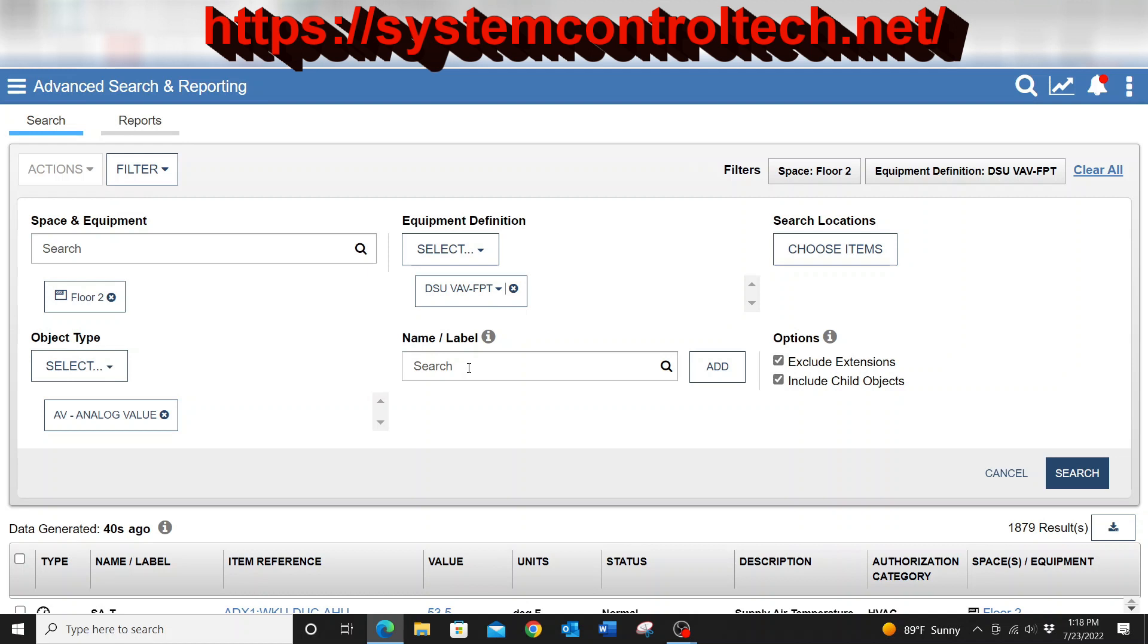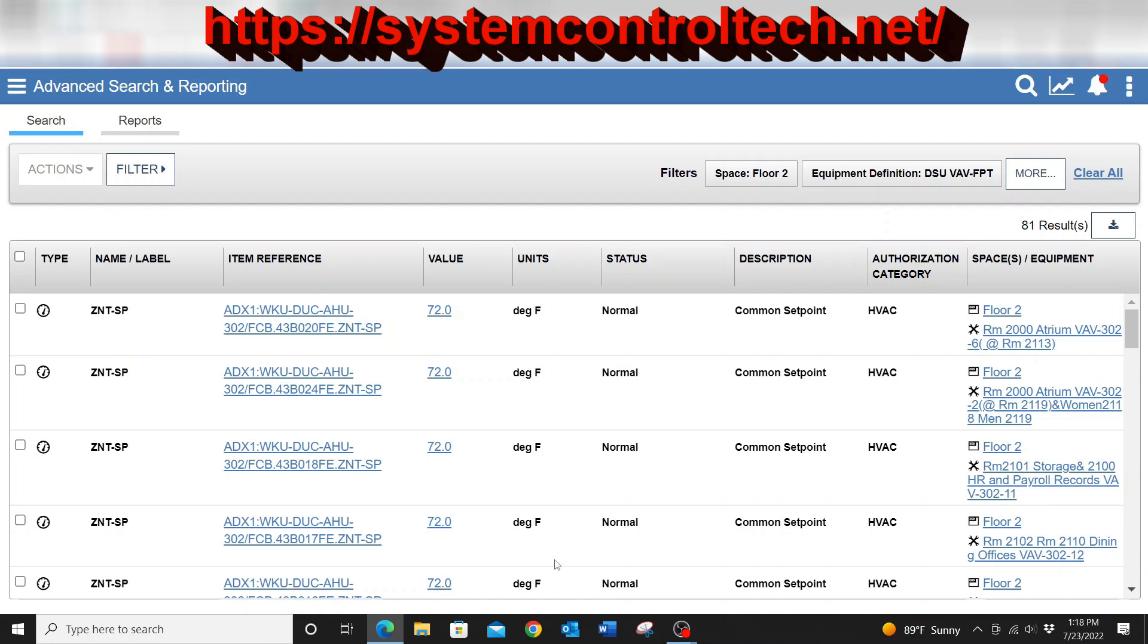The next thing that I'm going to do is type in the name of the particular point that I want, which is simply ZNT-SP. And when I add that, just like so, I can then press search. And once I press search with those criteria, you can see here that it will give me a list of every single one of the zone temp set points for this floor.